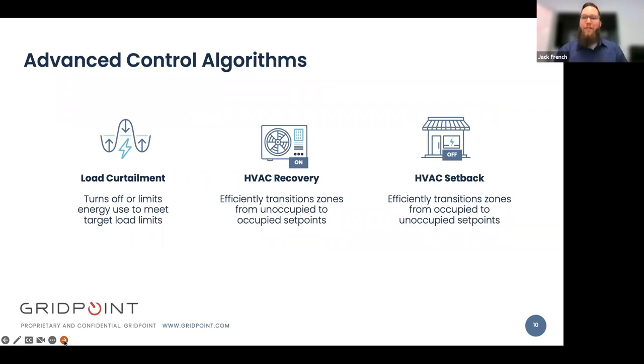So we also have some advanced control algorithms, and these are things that can be implemented to help marginally improve savings and also improve the lifespan of your HVAC equipment. Starting with load curtailment, it basically works by predicting when you're going to have a peak interval for your overall building's consumption. And when a predicted peak happens, the HVACs are allowed to drift usually 2 degrees from their occupied set point. So they'll drift 2 degrees in the energy conserving direction to not only reduce the severity of the peak, but also to reduce the runtime of the unit, which will help, again, extend the equipment's lifetime and is a more efficient way to run your building.